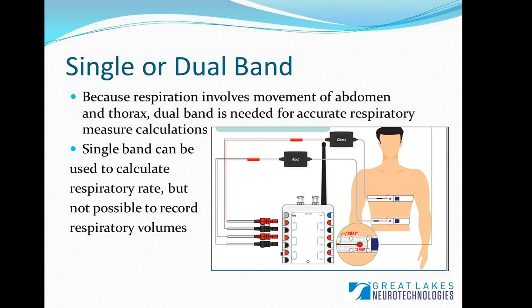This is what the RIP setup looks like — you can see bands worn around the chest. A common question is whether to use just one band around the thorax or two bands around the thorax and abdomen. Looking at the physiology behind respiration, it really involves movement of both the abdomen and thorax. Having both bands is needed to get accurate respiratory measurements, including volume, flow, and rate. With just a single band, you could calculate respiratory rate from the waveform, but you cannot accurately record respiratory volumes — so using two bands is really important.